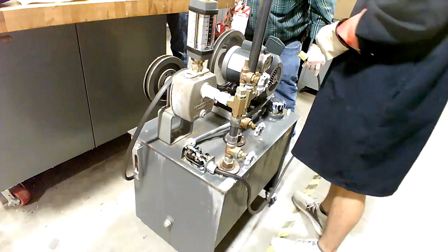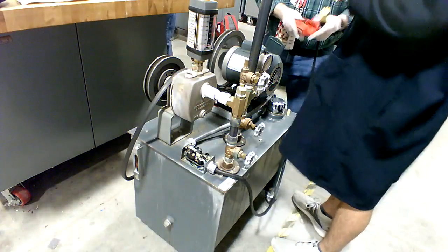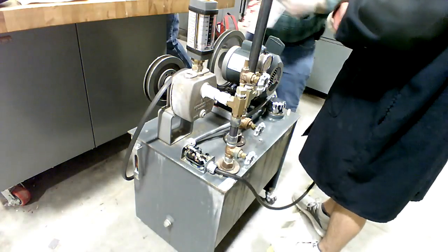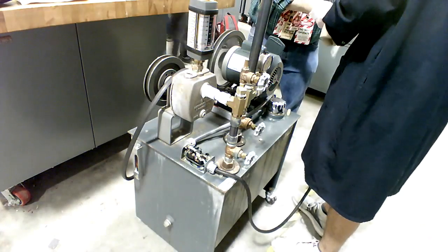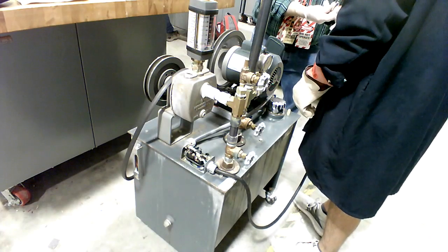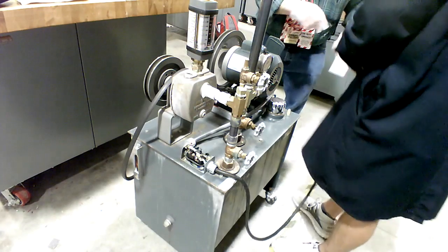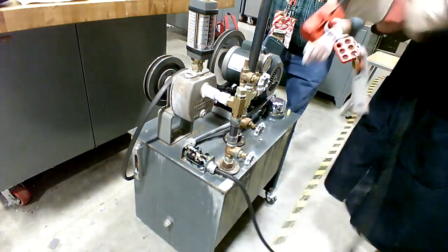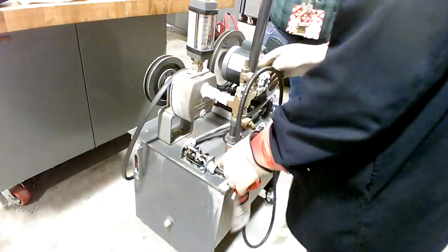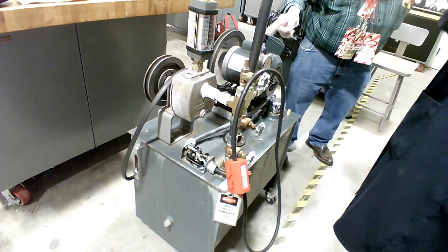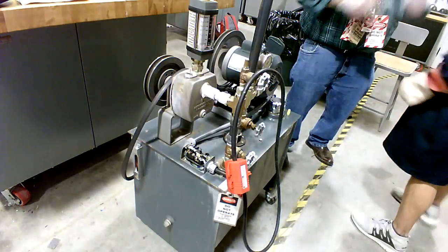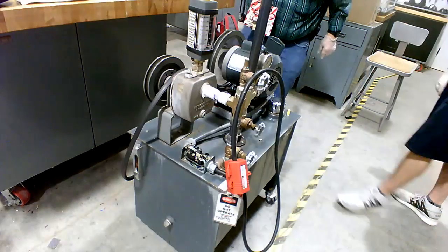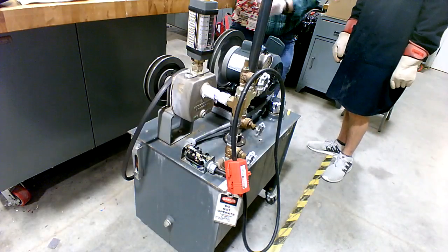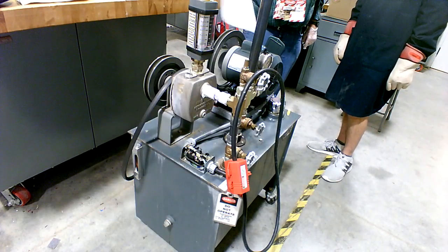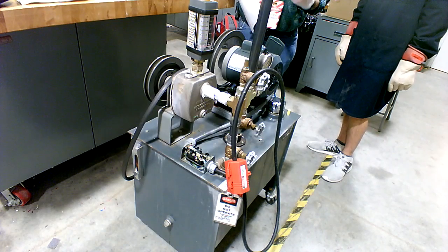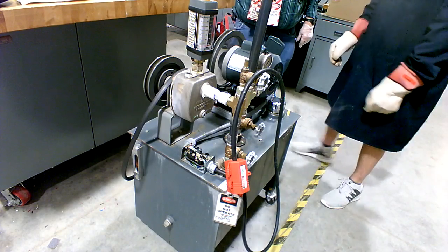You want to weigh it up here? Do that. That means to slow all the way down. Right now, it's going to generate voltage coming out of it. You'll just get a tangle in the windings in that motor right now. Those windings right there are freewheeling. It's going to be generating some voltage coming out there on this line.